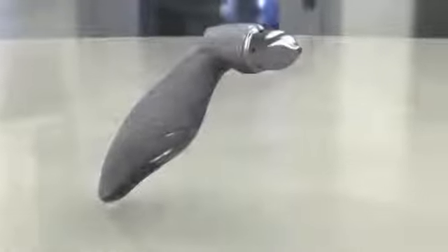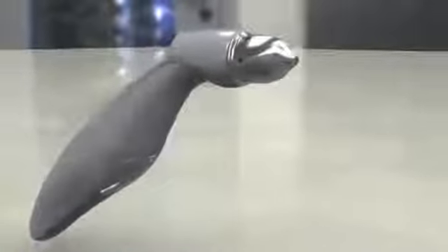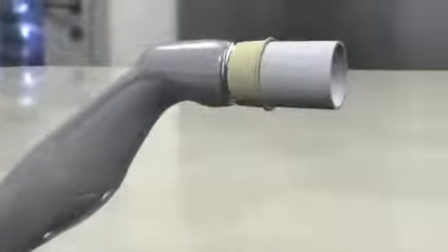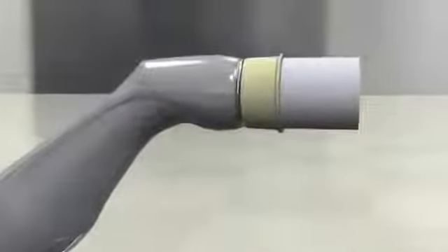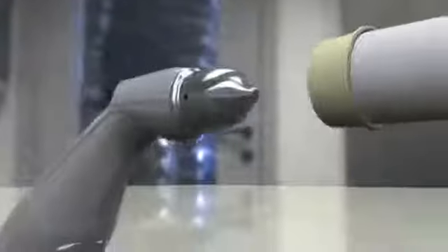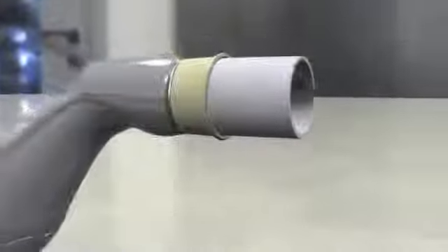Taking a measurement. After anesthetizing the patient, an AccuTip cover should be placed properly on the transducer. AccuTip covers eliminate cross-contamination and protect the transducer tip from dust and liquids that could potentially damage the unit. AccuTip covers can be purchased directly from Accutome or authorized Accutome distributors. Simply roll the cover on using the cardboard applicator.